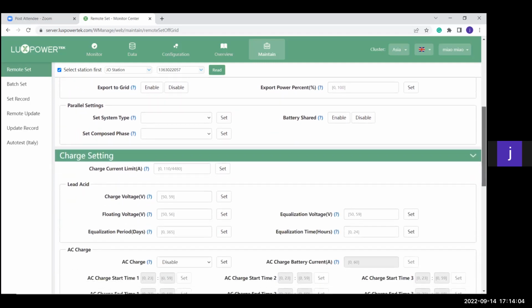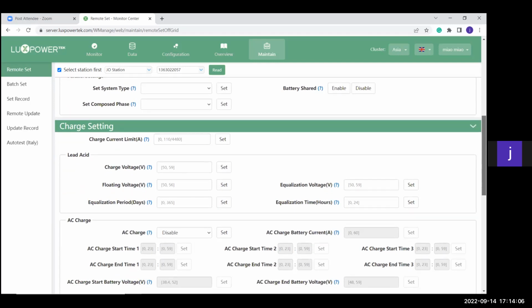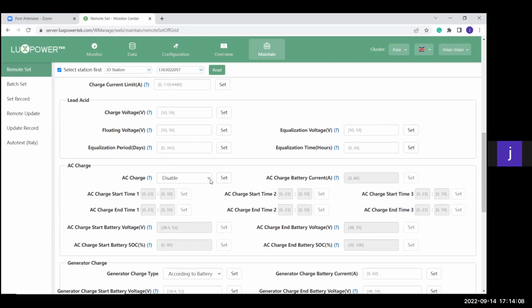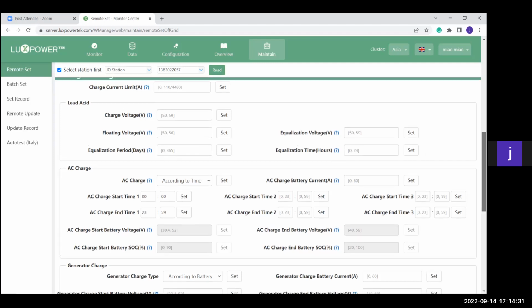Then the last thing that you have to activate on the UPS system is your AC charge. You press it according to time, and it will be the same, 0000 and 2359. And you press set after you are done with all your settings. It will tell you successful, and then it is set up to AC charge permanently, and it's a backup system.